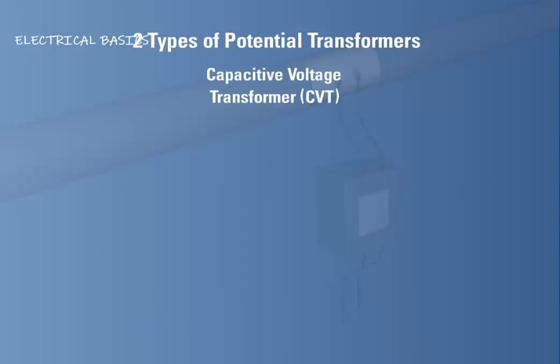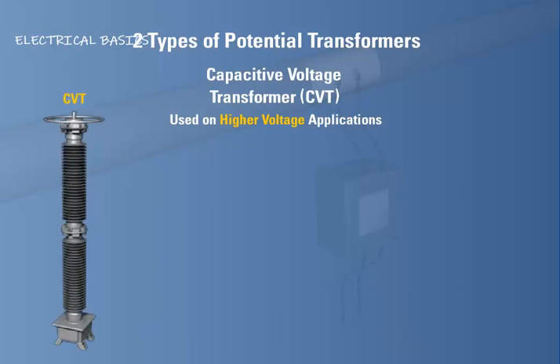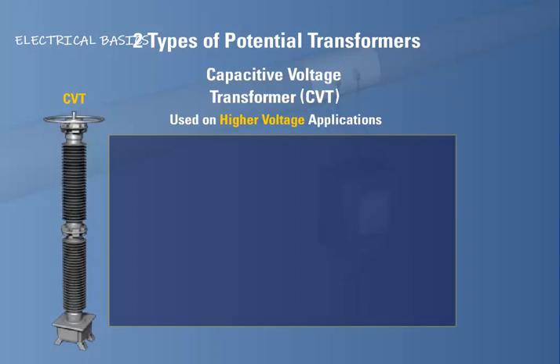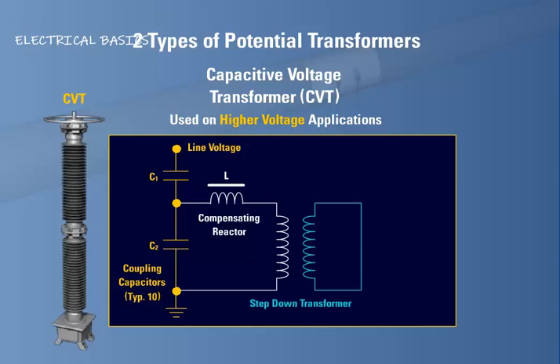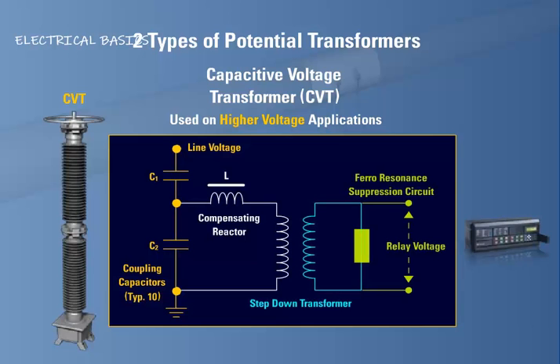Capacitive voltage transformers, or CVTs, are normally used on higher voltage applications. The CVT is basically a capacitance potential divider and consists of the following components: coupling capacitors, typically 10; a compensating reactor; a step-down transformer; and a ferroresonance suppression circuit found just before the output terminals for connecting to a relay.